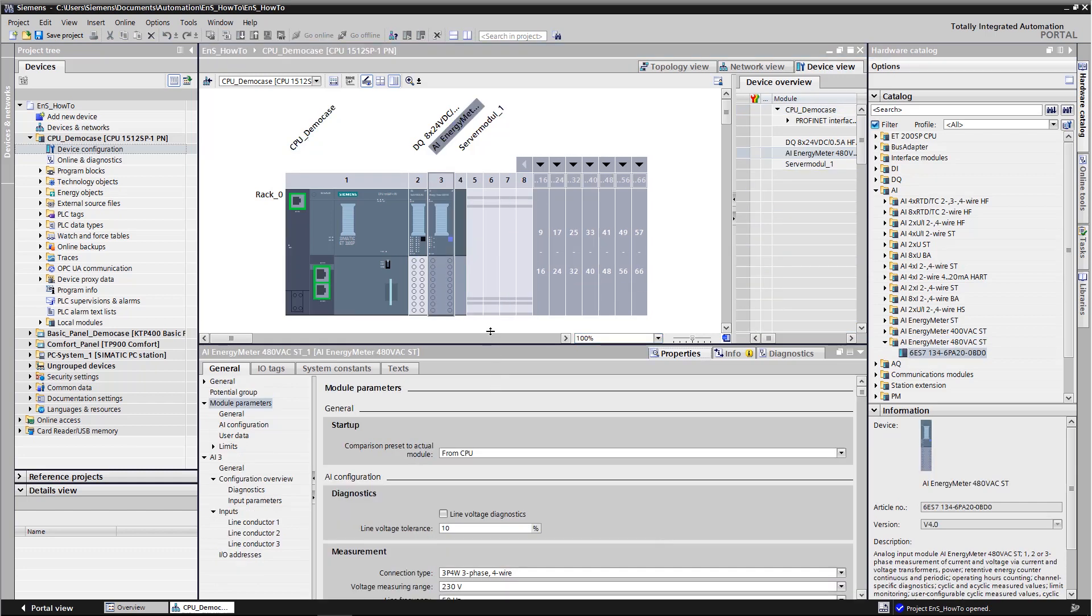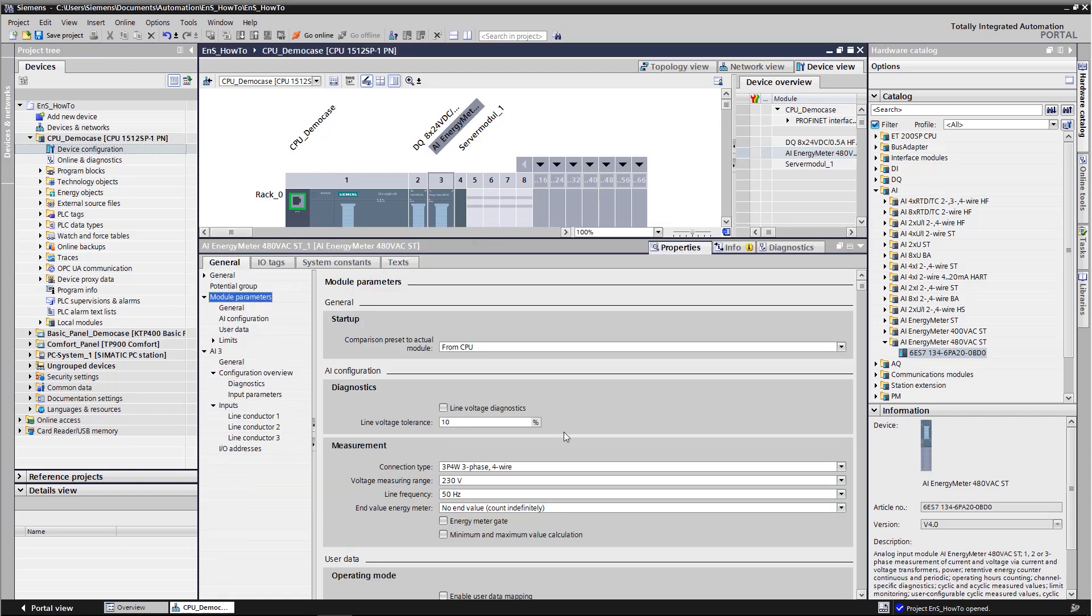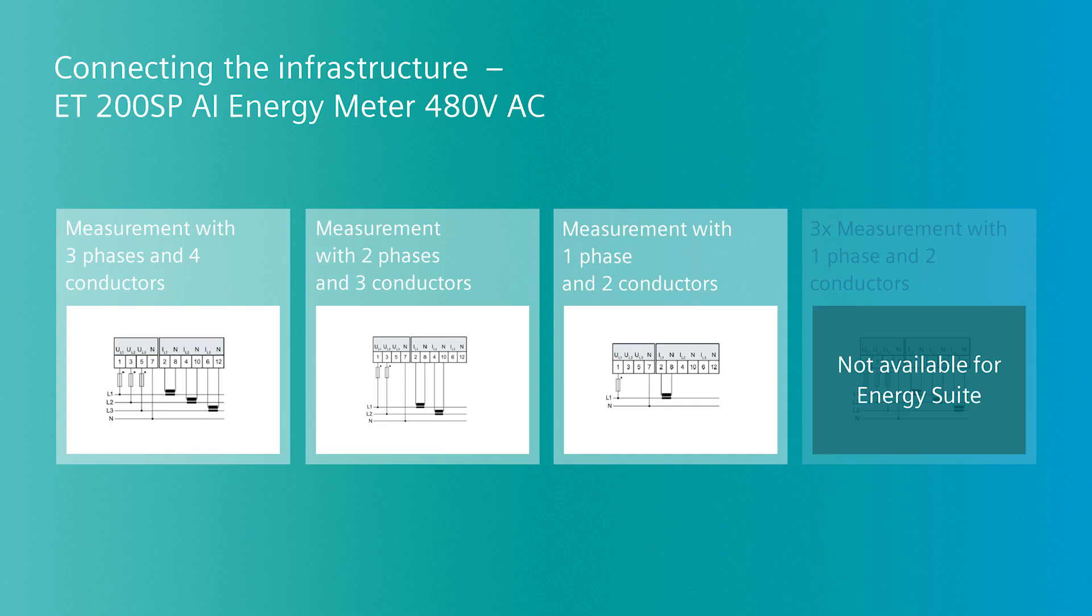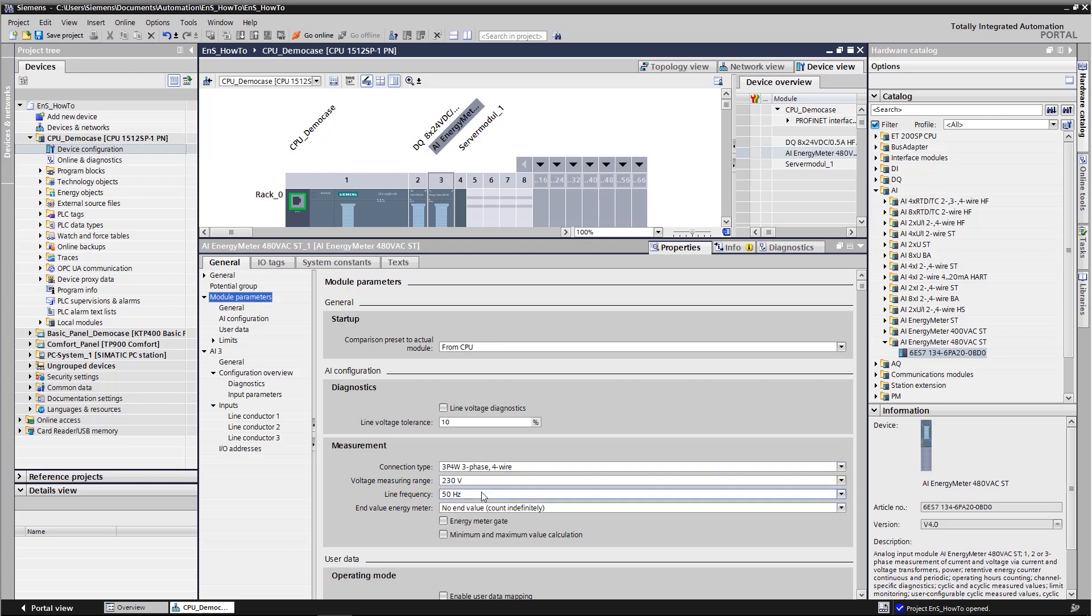Then we open the energy meter properties. We go to the measurement settings and choose the measurement type the energy meter should use. Here it is important to note that one of the four measuring types cannot be used if the energy meter is being used as an energy object in Energy Suite. That means no advanced data can be generated if you're using one energy meter to measure three measuring points, each with one phase and one neutral conductor. The reason is that the measurement is calculated for the energy meter as a whole.